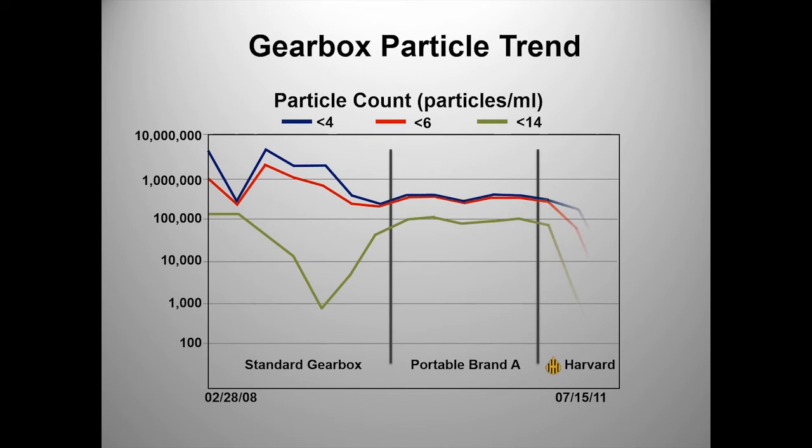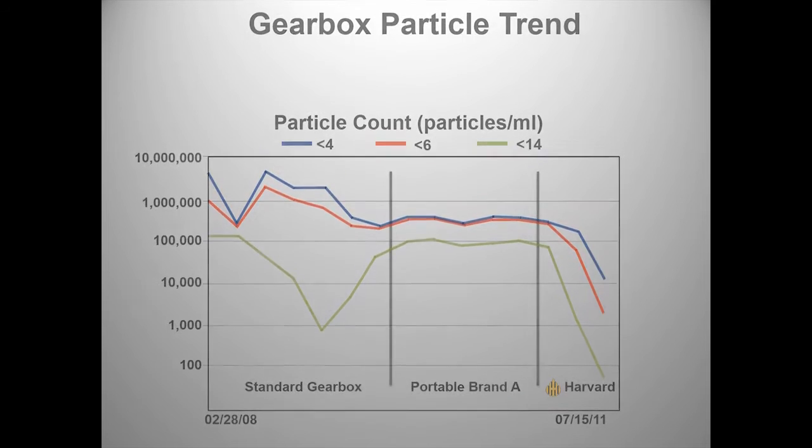Other filters couldn't bring the particle count below 100,000 particles per milliliter, but adding the Harvard filter cut the particle count by over 90%, reducing the count of particles under 4 microns to just over 10,000 and particles under 14 microns to less than 100.